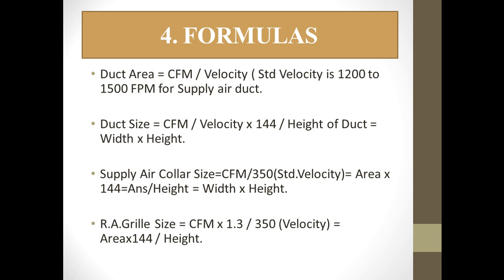To calculate the return air grill size: Return Air Grill Size = (CFM × 1.3) / 350. The factor 1.3 accounts for 30% additional area of the entire return air grill. Divide by the velocity of 350 FPM to get the area, multiply by 144 for square inches, then divide by the height to get the width — giving you the return air grill size.